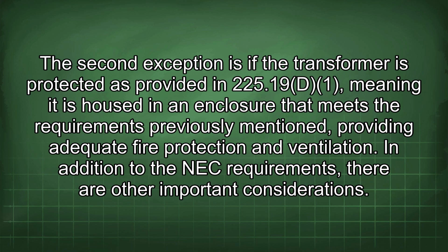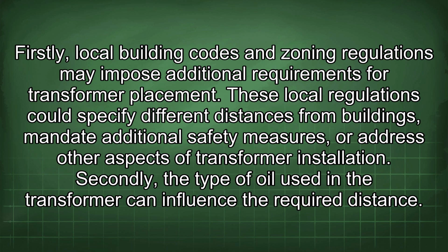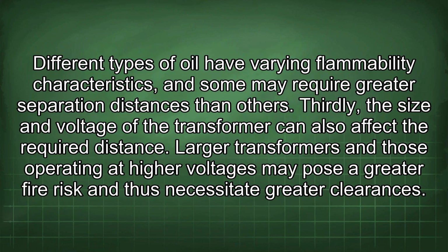In addition to the NEC requirements, there are other important considerations. Firstly, local building codes and zoning regulations may impose additional requirements for transformer placement. These local regulations could specify different distances from buildings, mandate additional safety measures, or address other aspects of transformer installation. Secondly, the type of oil used in the transformer can influence the required distance. Different types of oil have varying flammability characteristics, and some may require greater separation distances than others.